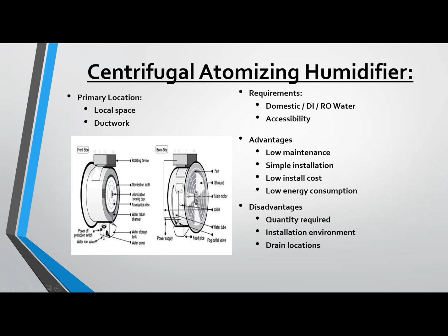Another disadvantage is drain locations. These require a drain, so you'll need drain piping, which can get tricky, especially in existing facilities. You need enough length and fall to exit excess water and drainage quickly and safely. Anytime you're dealing with interior drains it can get complicated, especially if you have leaks. But overall, these are very effective systems.